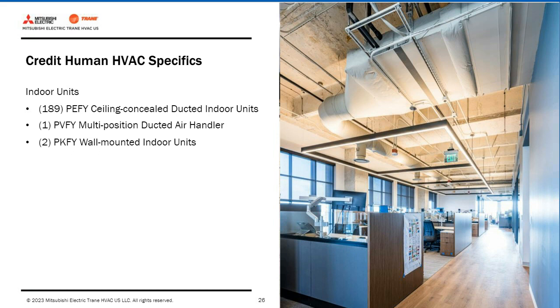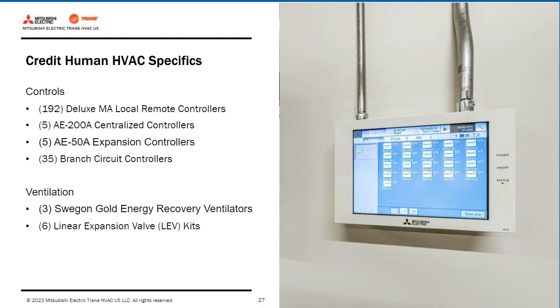As Jamie touched on, one of the great benefits of the VRF technology is the option for zoned comfort control. Each zone is able to have its own set point based on occupancy, usage, or personal preference. In the Credit Human office space, the system is controlled through a singular interface, but thermostats can be found throughout the space about every 20 feet apart, giving employees some autonomy over their comfort. So you can adjust these individual zones, even though it's an open office space. Some of these zones can still have some local control, depending.